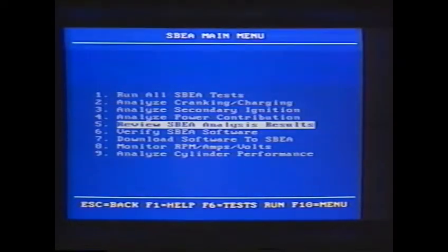The cylinder performance test gives you the percentage performance cylinder by cylinder. Selecting number 8, Monitor RPM Amps Volts, is a quick way to check the generator and battery condition.